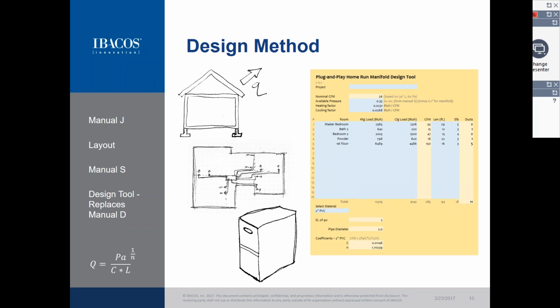You would still need to perform a standard system selection, so your manual S, and out of that process you also are able to understand the amount of static pressure that's available to the system. And then where the new approach comes in is when it comes to the duct design. So that manual D, instead of needing to consider the trunk and branch conventional system with various fittings and duct sizes, this design approach instead, based on that available static pressure, is able to predict the amount of airflow that would go through each duct runout, and then select the number of ducts that are needed for a room.